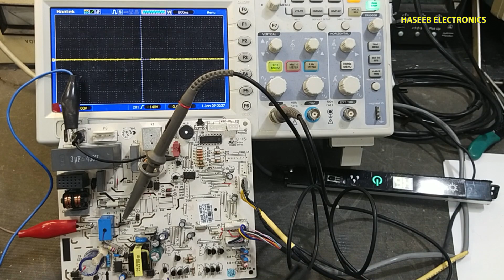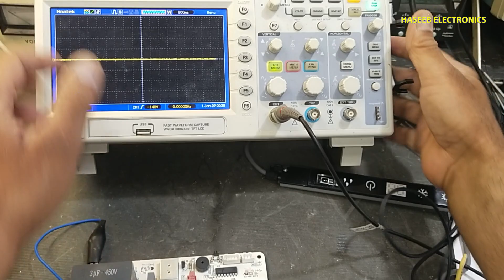Here it is providing voltage to the fan motor, but there is no fan motor. When there is no fan motor, we will not receive any feedback here. Let me power it off. I will disconnect the oscilloscope now. If you have a bad optocoupler, at that time it will not send this signal to the outdoor unit.